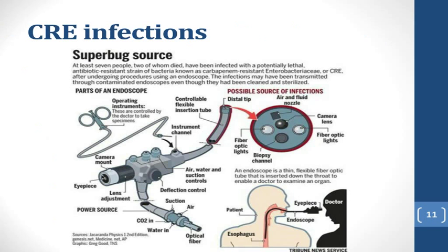These little bugs that would hide in crevices and stuff, what you would normally do is use an enzymatic chemical bath and basically scrub the endoscope and soak it for a while, and then you would be able to say, okay, it's sterilized, you can use it on the next patient. Well, because it appears that that particular approach is not adequate, the hospital now will send the product out to a reprocessor, which is a specialty kind of a service company, and they use gas sterilization to clean these duodenoscopes.